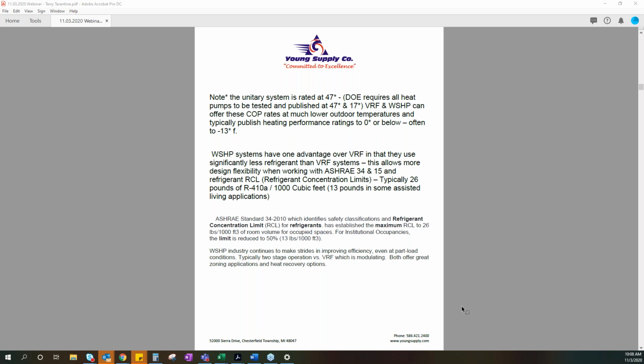47, where did we get that from? The Department of Energy requires all heat pump manufacturers to rate their equipment at 47 and 17. So you'll always see those performance data out there. But typically when you're getting into the VRFs and the water source heat pumps, you'll find publications down to 0, -13. Some of them have gone significantly lower. We'll see an example of that in a little bit.